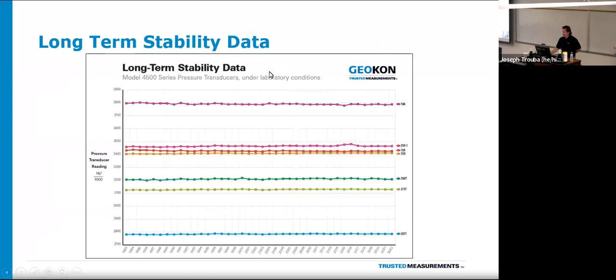This is a table from our laboratory. So we've been around for 40 plus years. These are our model 4500, which is a piezometer, so pressure transducer. And these have been under laboratory conditions for about 40 years. This graph goes back to 1983. We take periodic measurements on these instruments, usually annually. This is an annual chart.